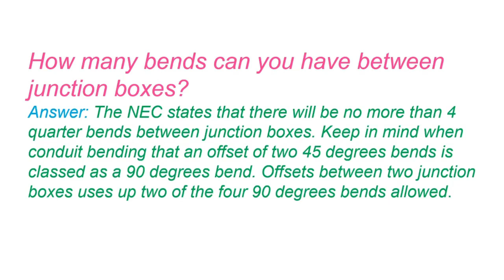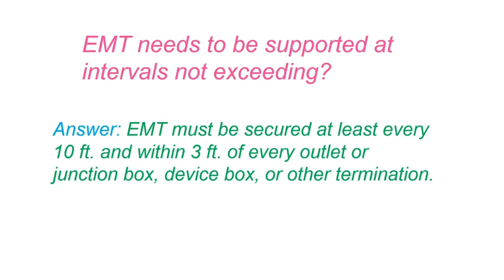EMT, or electrical metallic tubing, needs to be supported at intervals not exceeding what? EMT must be secured at least every 10 feet and within 3 feet of every outlet or junction box, device box, or other termination.